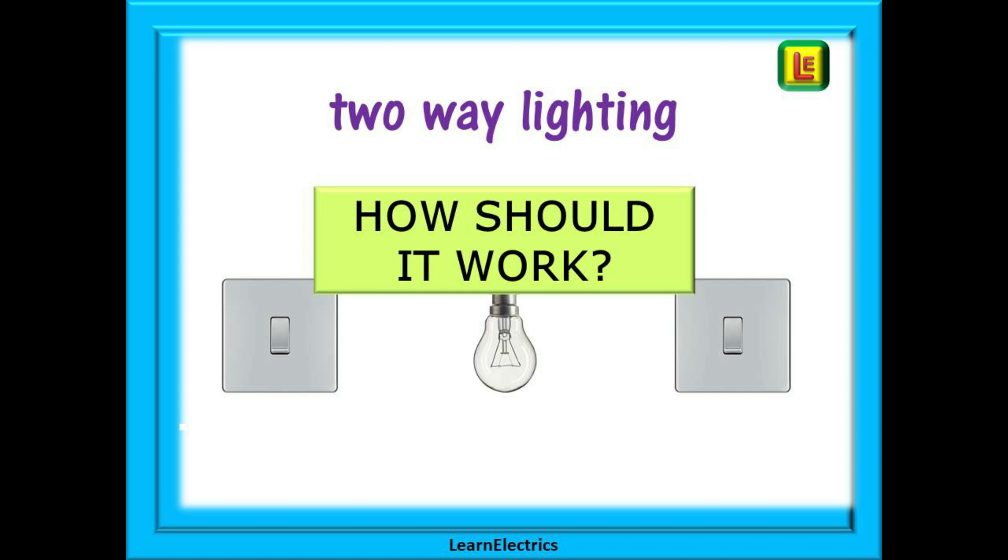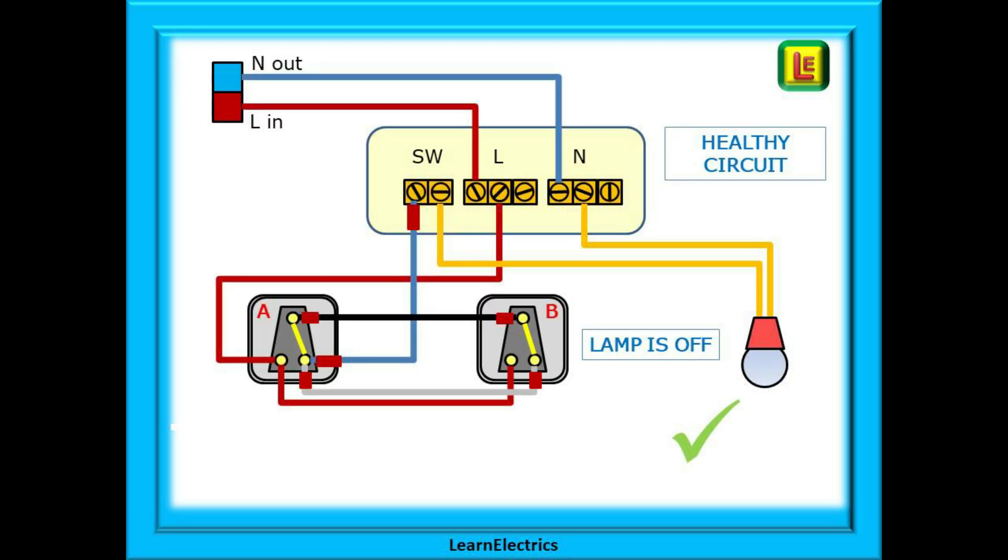Now let's look at two-way lighting and first, again, we will consider how it should work in a healthy, fault-free circuit. These healthy circuit drawings will have a green tick on them. In this example, electric enters the circuit at the top left, as before, into the live loop block and then from the live loop along the brown wire to switch A. But from switch A it cannot get any further. The switches are in the wrong positions and so the lamp is off.